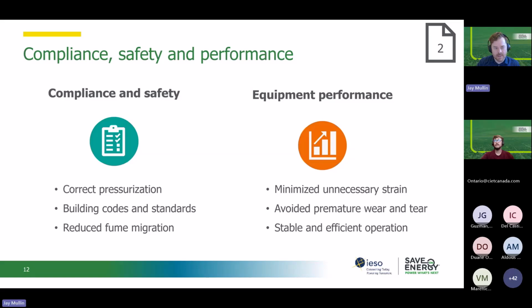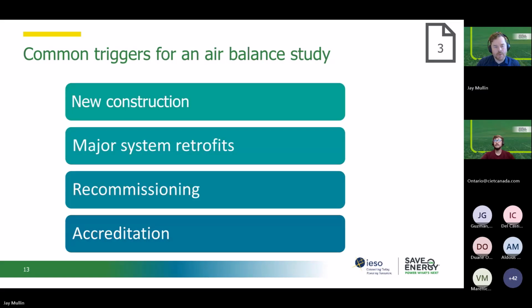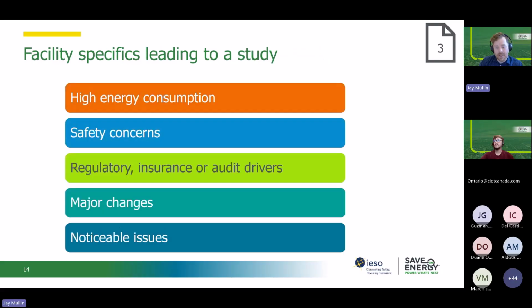So when we're thinking about getting these done, usually facilities will conduct air balance studies when there are significant changes to the building or the HVAC system, like new construction, major retrofits, or when recommissioning is taking place. It'll be part of that. It may also be required as part of accreditation for regulated operations. For instance, pharmaceutical facilities may need to verify the level of air changeovers and pressure differentials in their production area, that they're meeting defined standards, and that may have to be done on a certain cadence. But there are other reasons why you might be interested in conducting an air study.